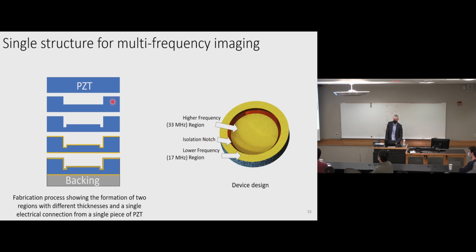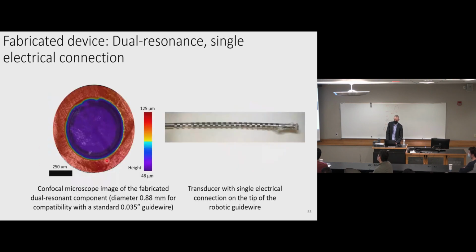On the left, we can see the cross-section of this. We start with the bulk PZT device. Then we use laser micromachining to remove some of the material, and that's how we make the 2 different thicknesses. We cut this isolation notch with the idea being to reduce the cross-coupling, or reduce the vibrations, between the high frequency on the outside, the low frequency on the outside and the high frequency in the middle. Then we metalize and we add our acoustic backing, and then we mount that device onto the end of that robotically steerable guide wire. It still only has one electrical connection here. You can see the image of this, the photo with the microscope scan overlaid. And so in the middle, this device, which is the high frequency part, is about 65 microns thick.